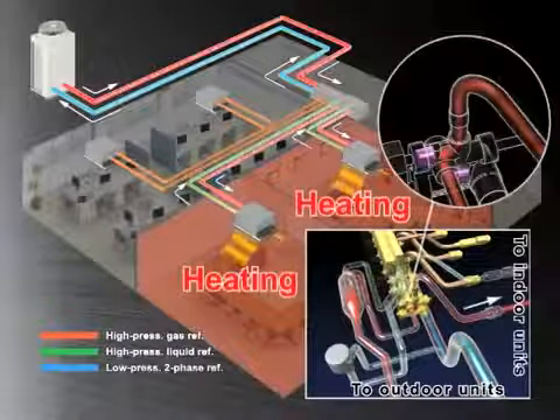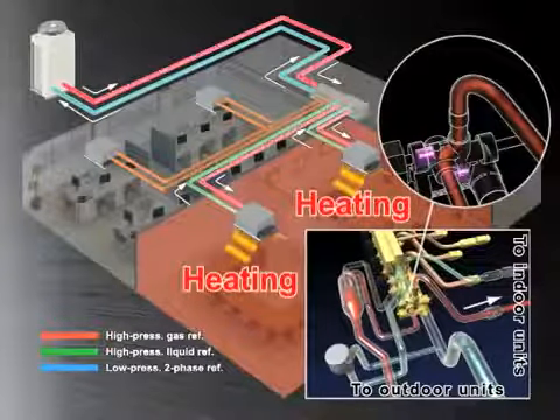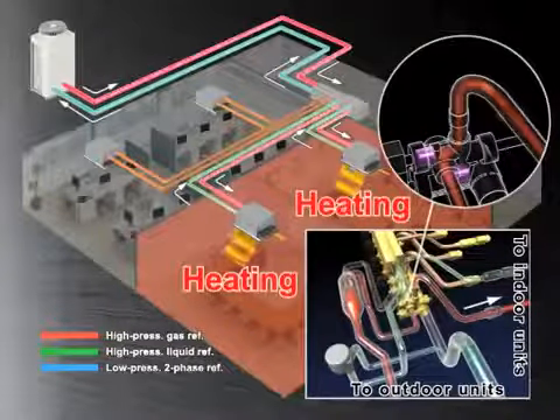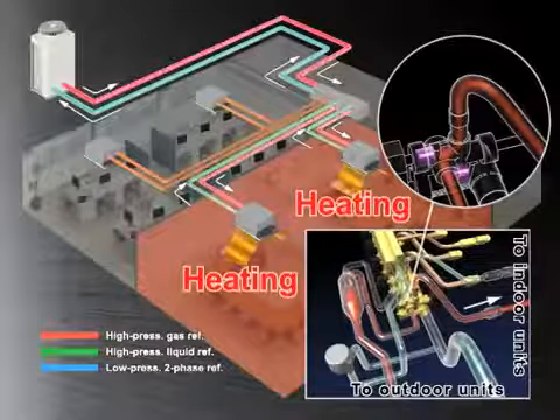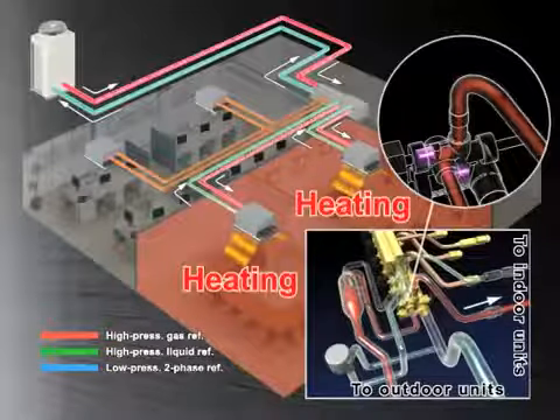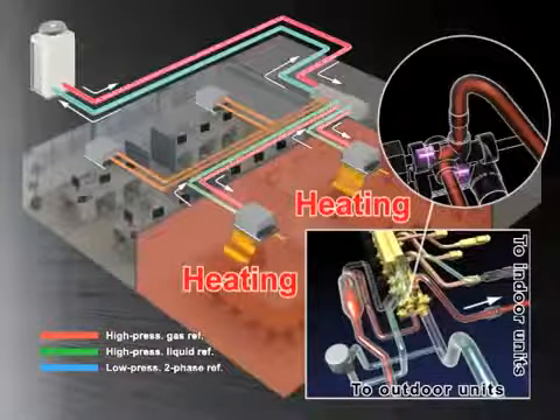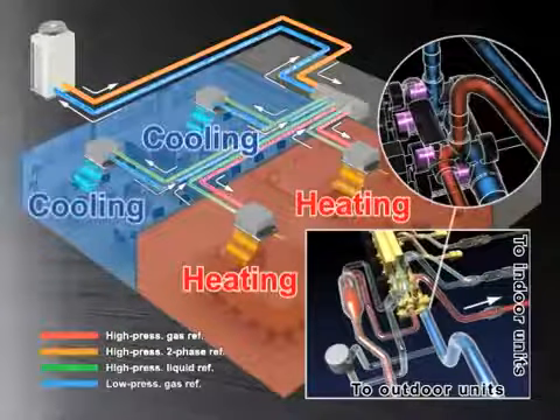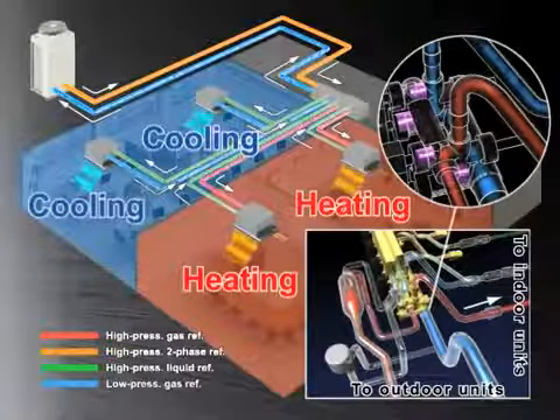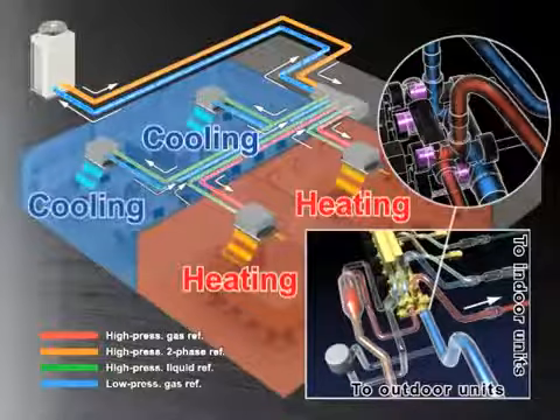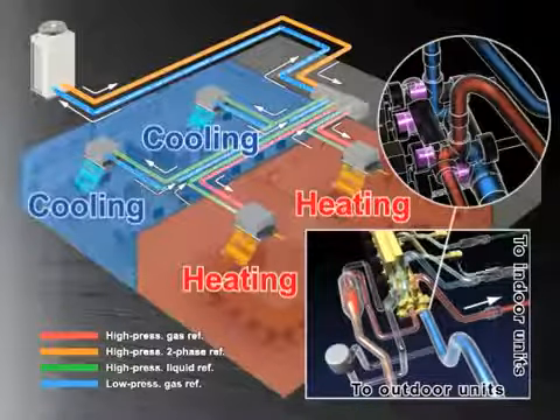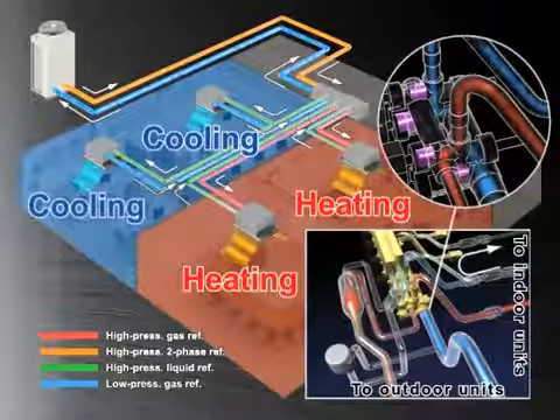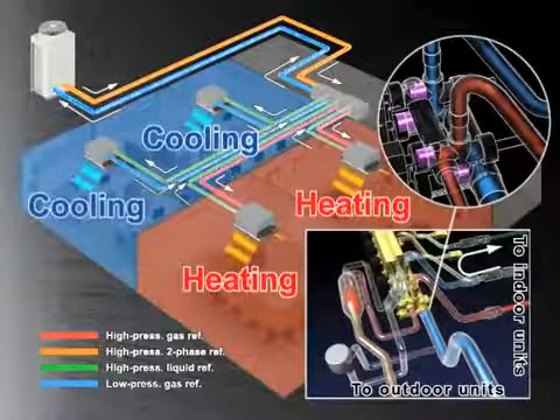Gas refrigerant is delivered to the indoor units in heating mode. If heating and cooling are required in the same system, the LEV switches the refrigerant flow. The gas refrigerant delivered to the indoor units in heating mode circulates back as condensed liquid refrigerant and is then delivered to the indoor units in cooling mode.